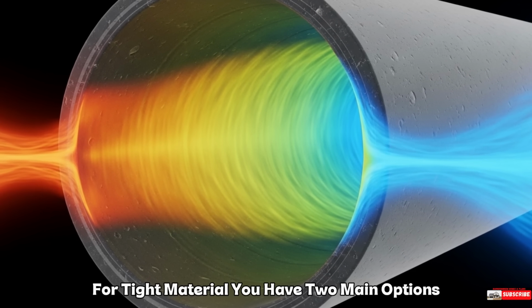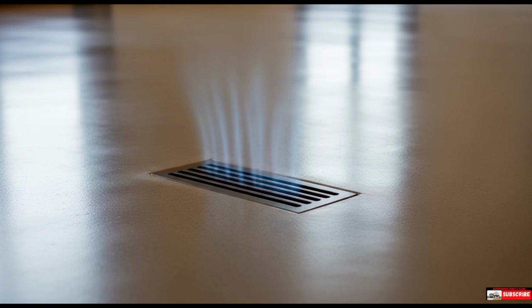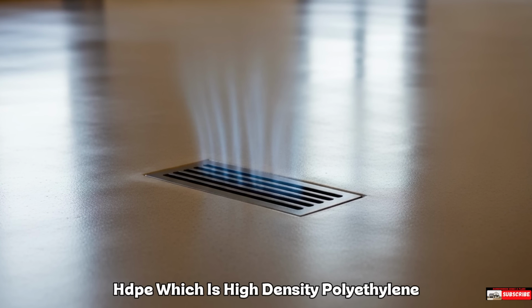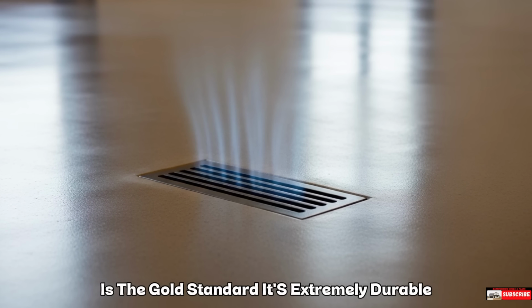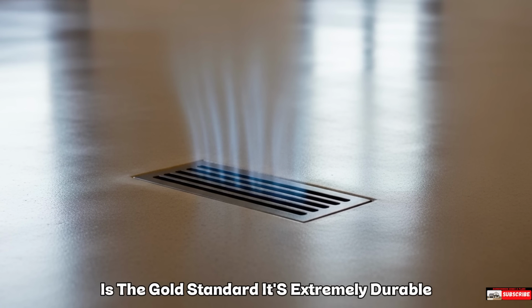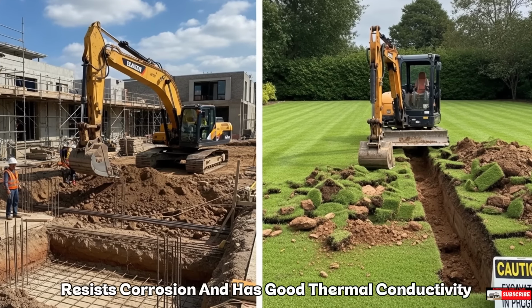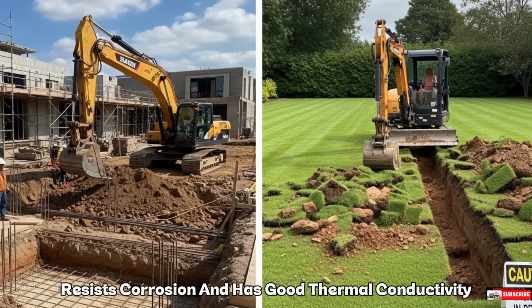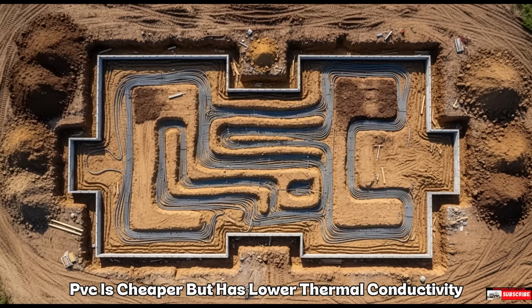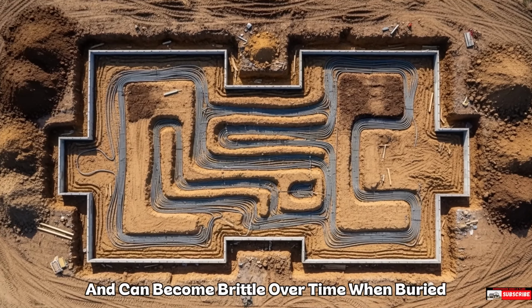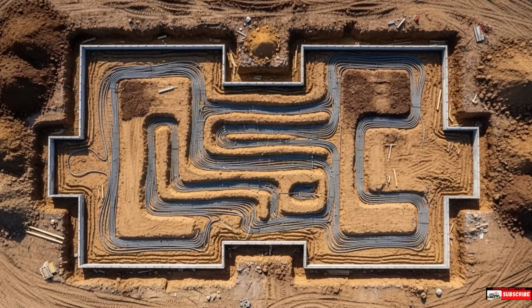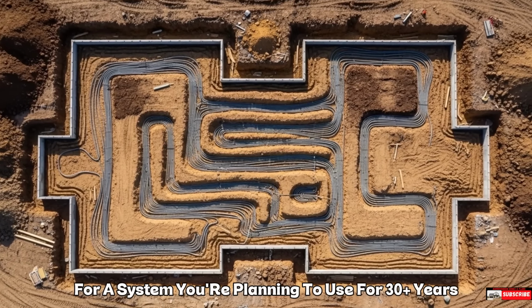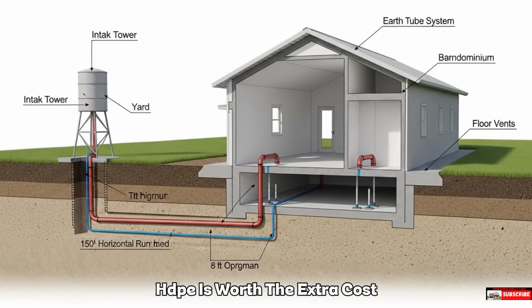For pipe material, you have two main options. HDPE, which is high-density polyethylene, is the gold standard. It's extremely durable, has a smooth interior for better airflow, resists corrosion, and has good thermal conductivity. PVC is cheaper but has lower thermal conductivity and can become brittle over time when buried. For a system you're planning to use for 30+ years, HDPE is worth the extra cost.